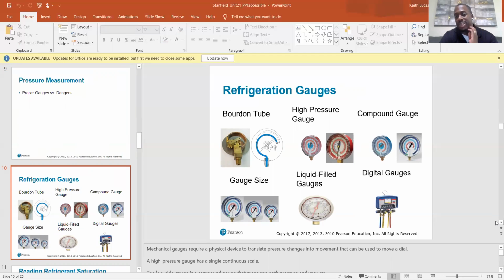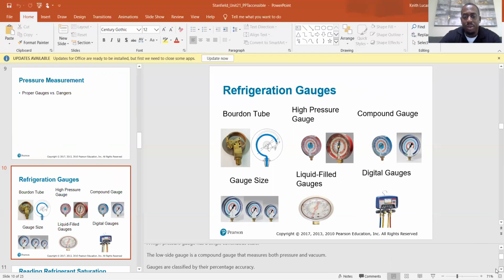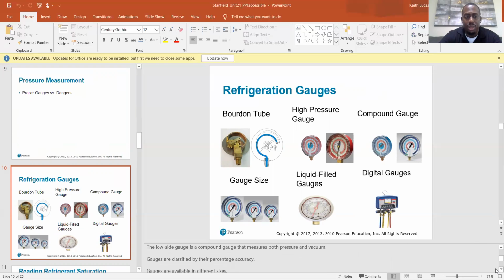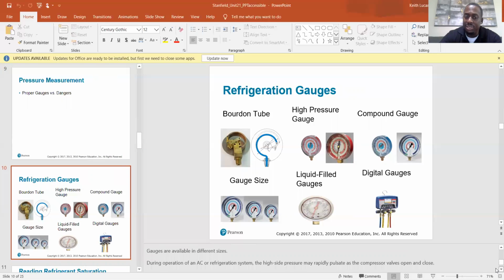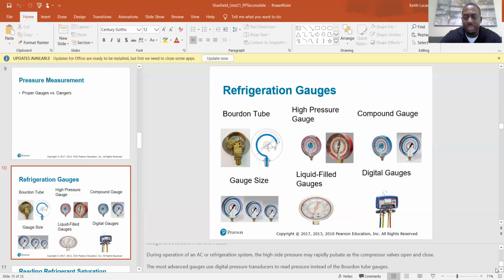So these are some refrigeration gauges. Mechanical gauges require a physical device to translate pressure changes into movement that could be used to move a dial. A high pressure gauge has a single continuous scale. The low side gauge is a compound gauge that measures both pressure and vacuum. Gauges are classified by their percentage accuracy. Gauges are available in different sizes. During operation of an AC refrigeration system, the high side pressure may rapidly pulsate as the compressor valves open and close. The most advanced gauges use digital pressure transducers to read pressure instead of the Bourdon tube gauges.